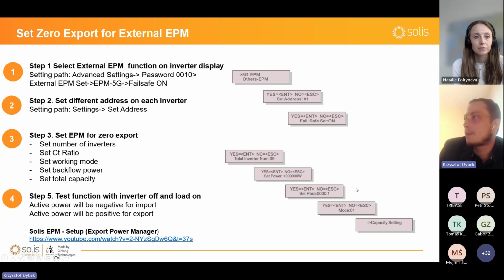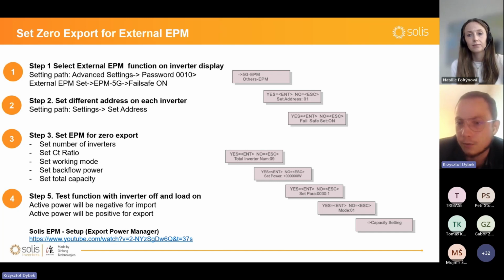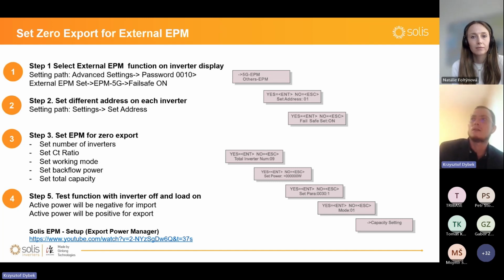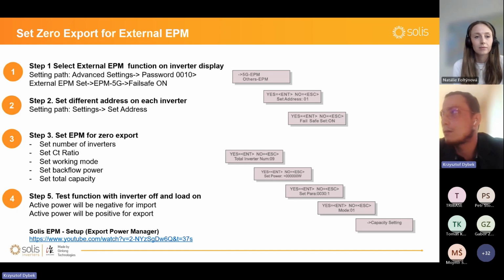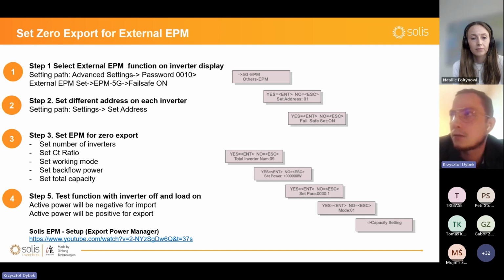And mode 2 is per phase, means that EPM takes into consideration lowest load value. So if, for example, on one phase load is equal to 0, it won't allow to produce anything. Not necessary in most cases, but sometimes grid operators require that. Like for example, in Spain, this is crucial. They do not allow to send anything to the grid, even if the sum is 0. So set backflow power here, this is just your limit. If you don't want to send anything to grid, set here 0 or even minus 100.